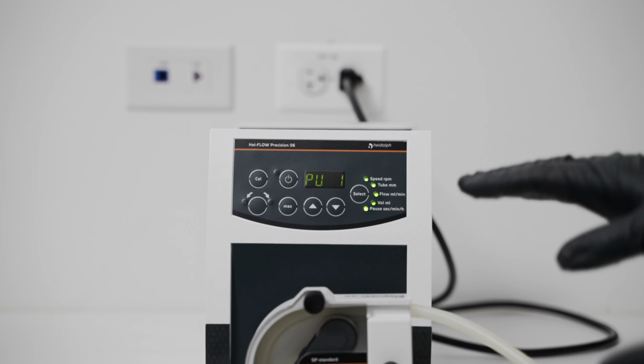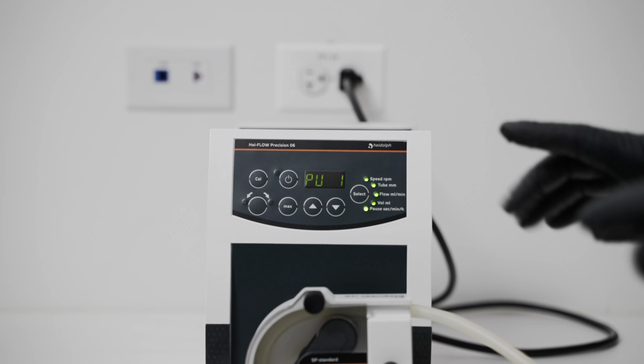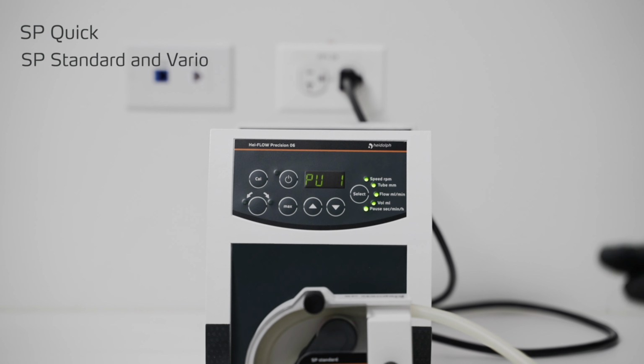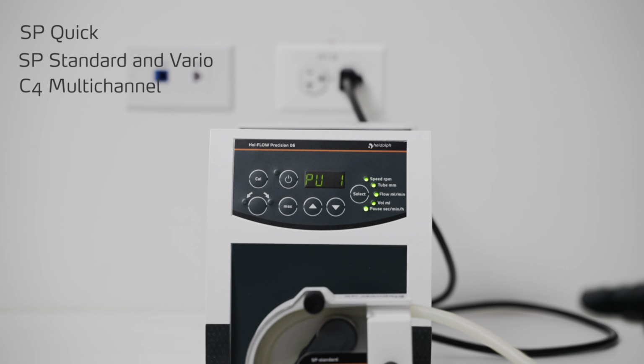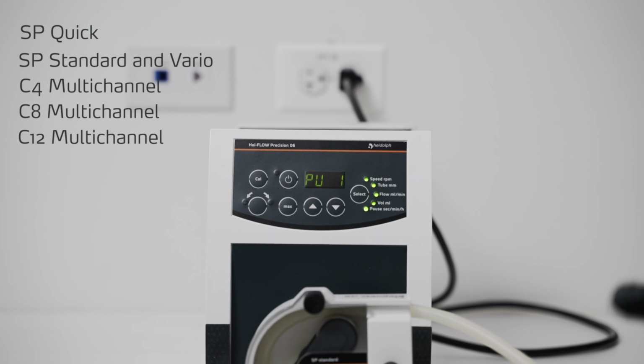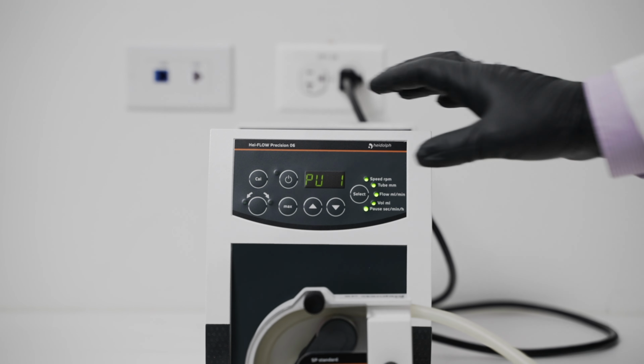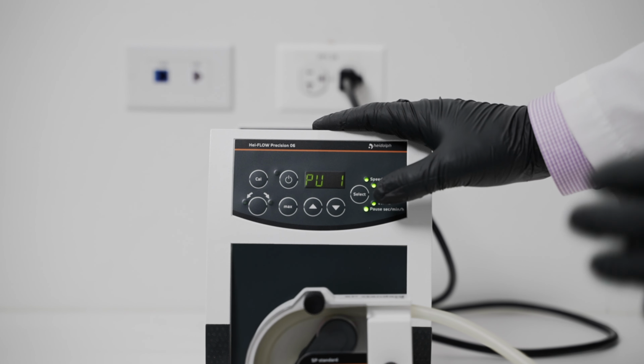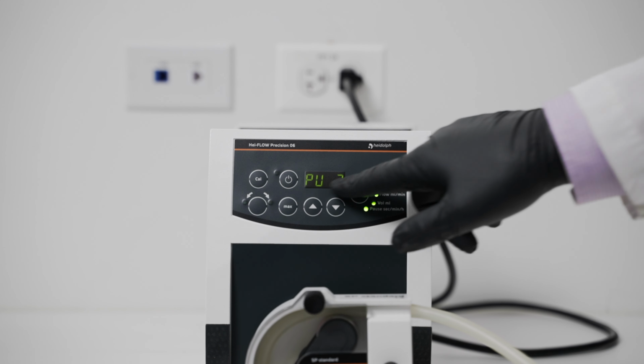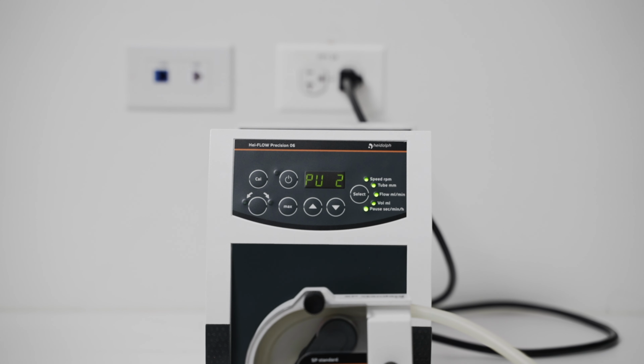Your options for setting the pump heads include the SP Quick, the SP Standard and Vario, the C4 multi-channel pump head, the C8 multi-channel pump head, and the C12 multi-channel pump head. Since we're using the SP Standard pump head, we're going to move up to PU2, as that is what corresponds to that pump head. For the full list of what setting corresponds to what pump head, you can refer to page 18 in your peristaltic pump manual.